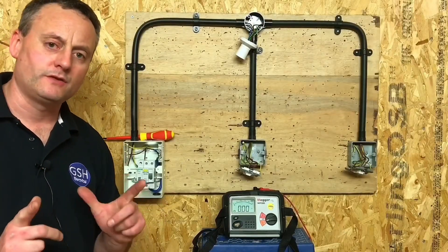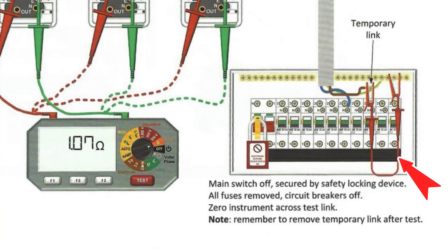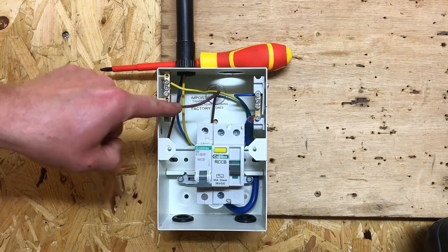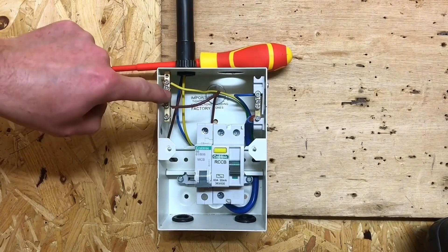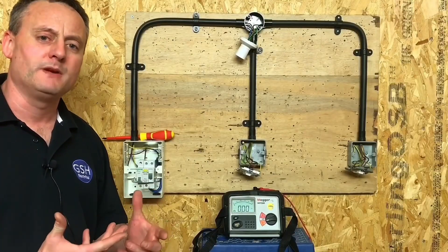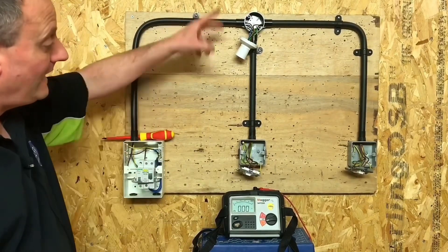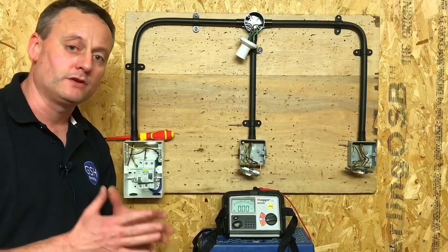A subtle difference from some of the video presentations I've done before: we aren't using the crocodile clip to link our line to our earth bar where our CPC is connected. We've actually physically put the line conductor into the earth bar where the CPC is connected, in order to make a solid link. We're finding that our links at college are becoming a bit unpredictable on our resistance reading, so we link those in the consumer unit slightly differently than before and go to each point in circuit in order to measure the continuity of the CPC.